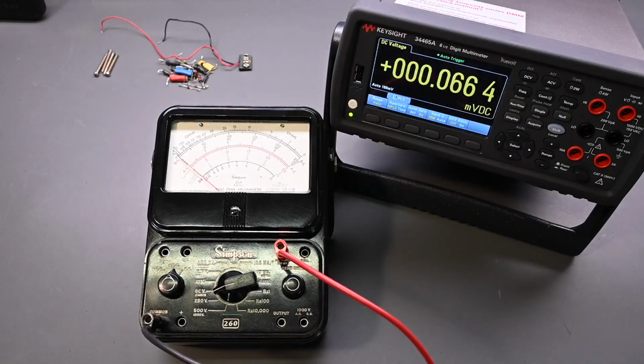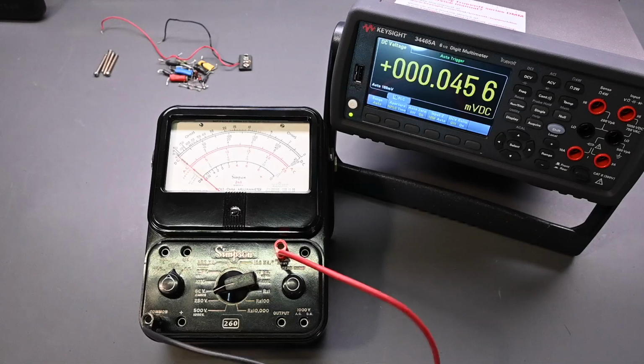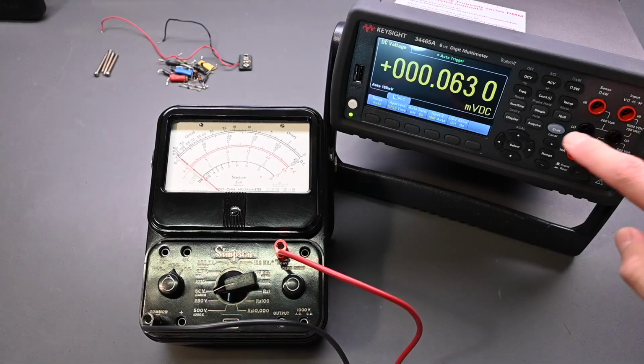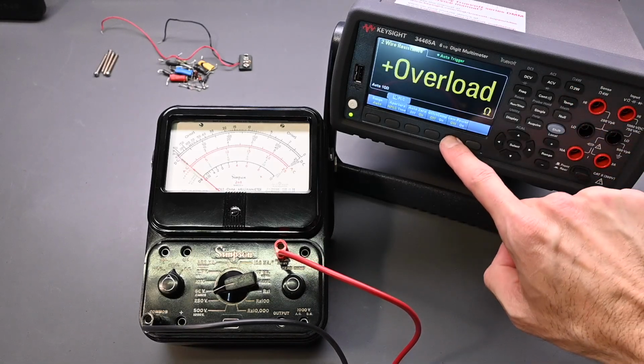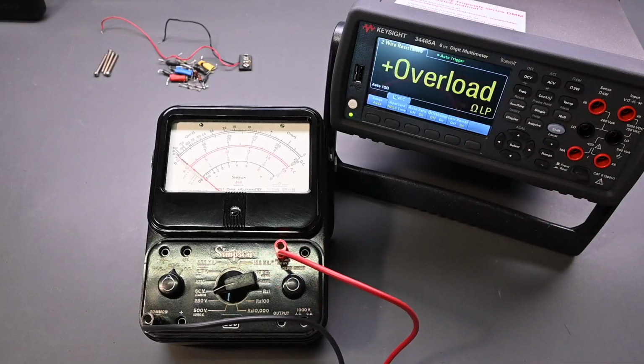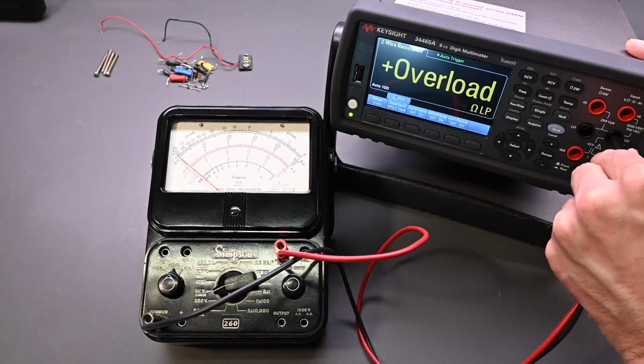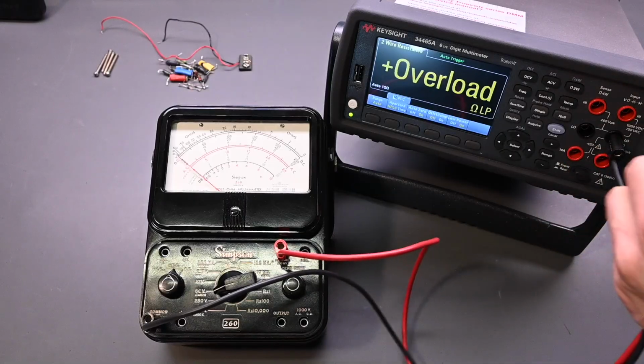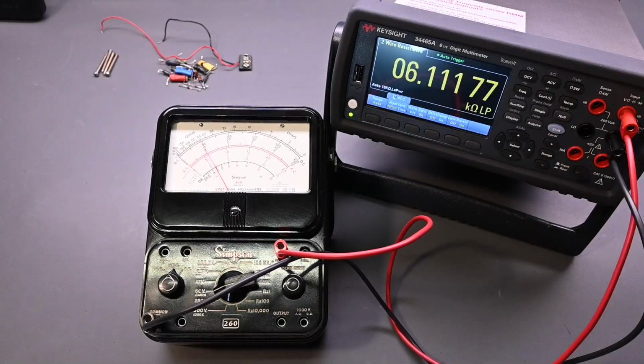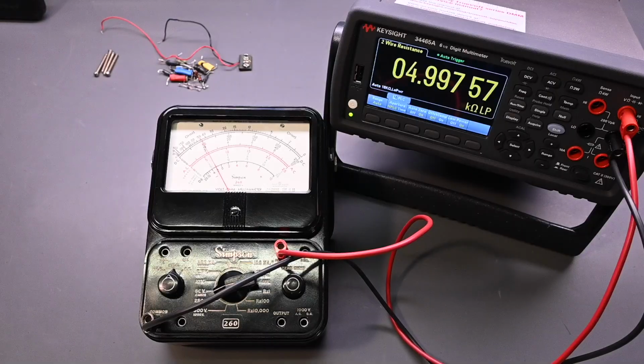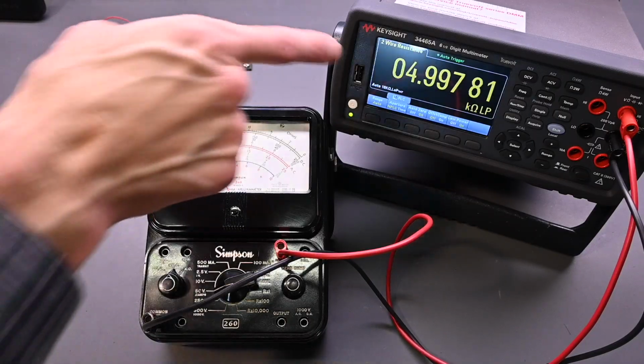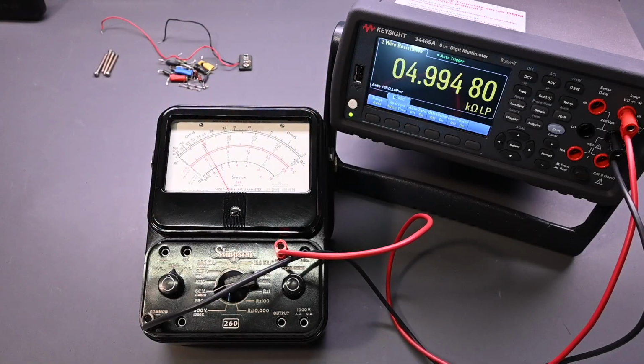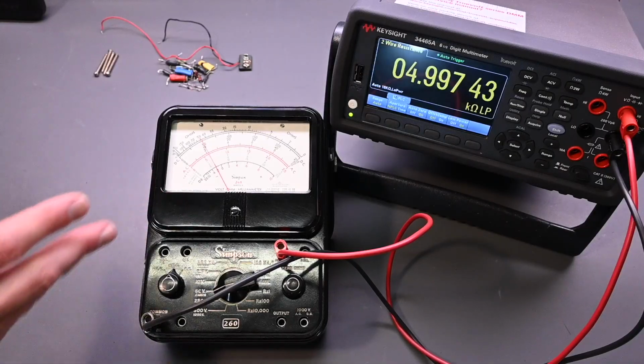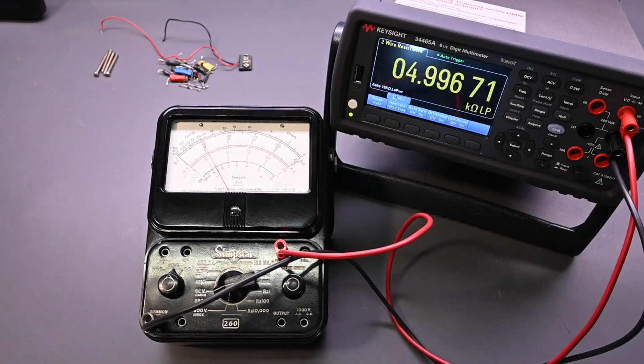So over here, let's give an extra twist on those leads and go to resistance mode. I'm going to start on low power because this is very sensitive on this first range. There. All right, so what do we have here? Looks like about 5,000 ohms. Perfect. So that's exactly what we want to see. So very, very close. It's really reading exactly right on. And in the part 1 video, when I did this test, that was way off. So it's a good start.